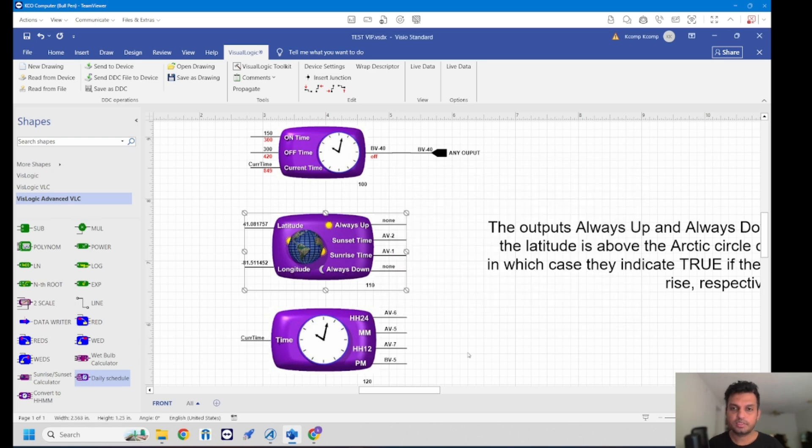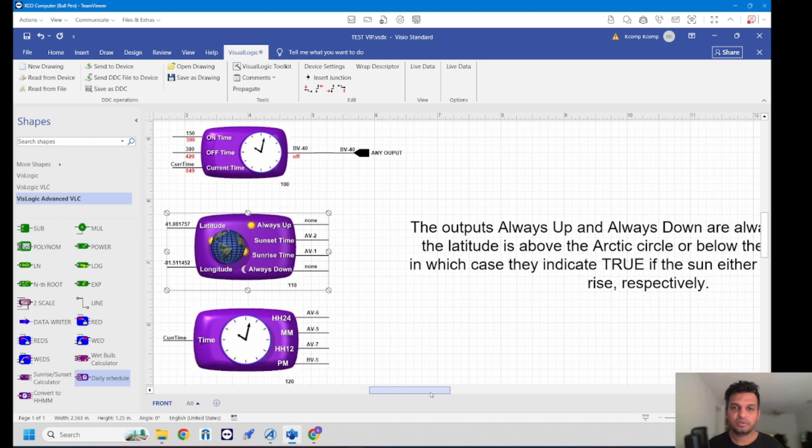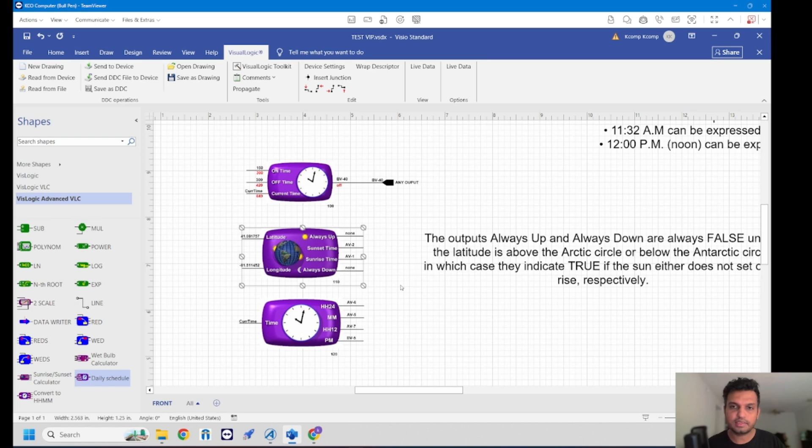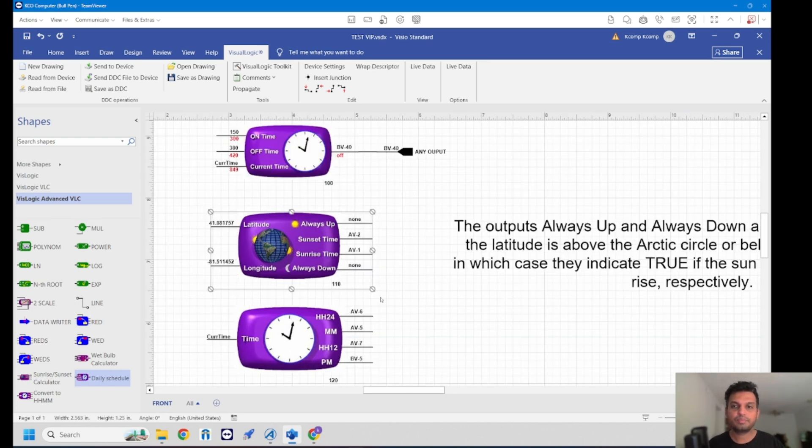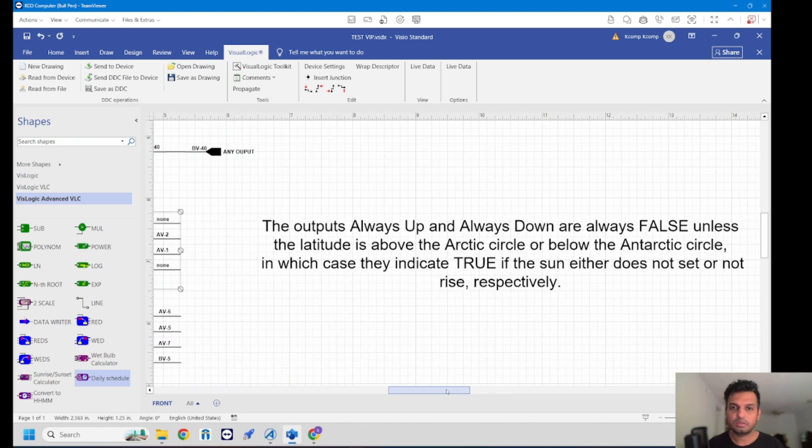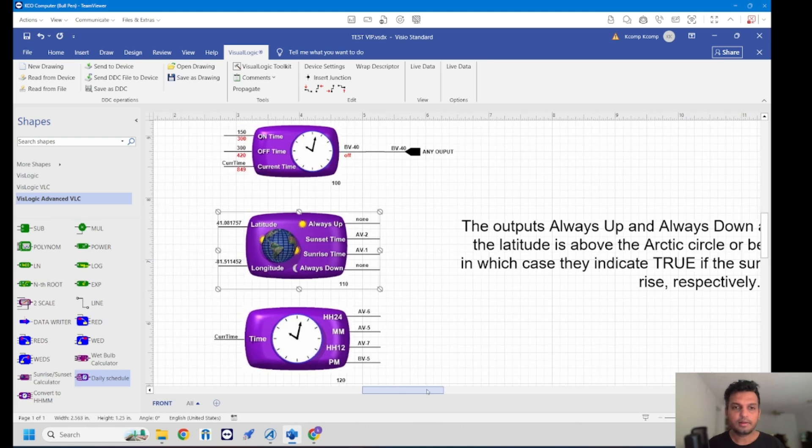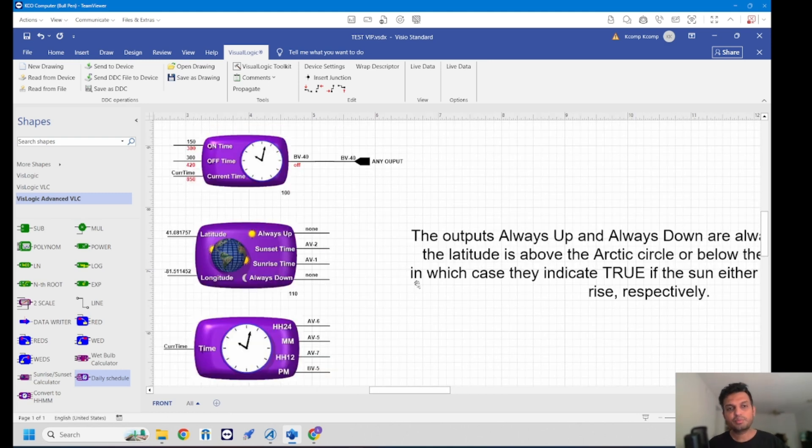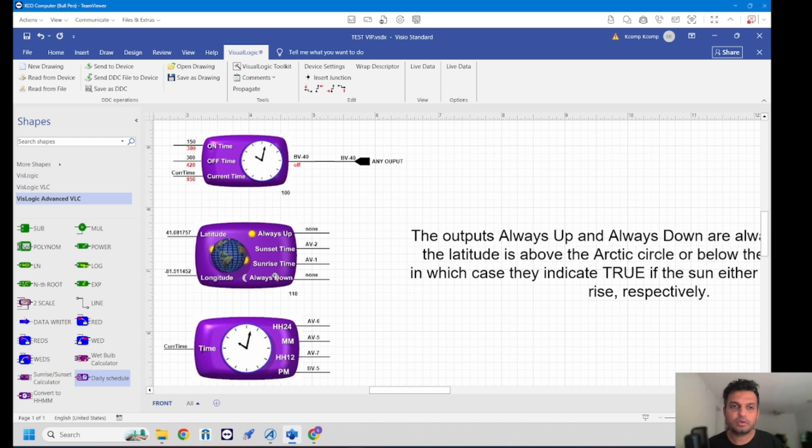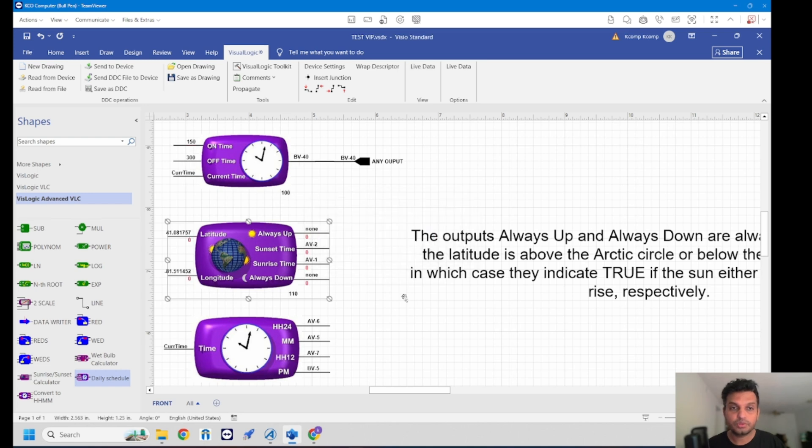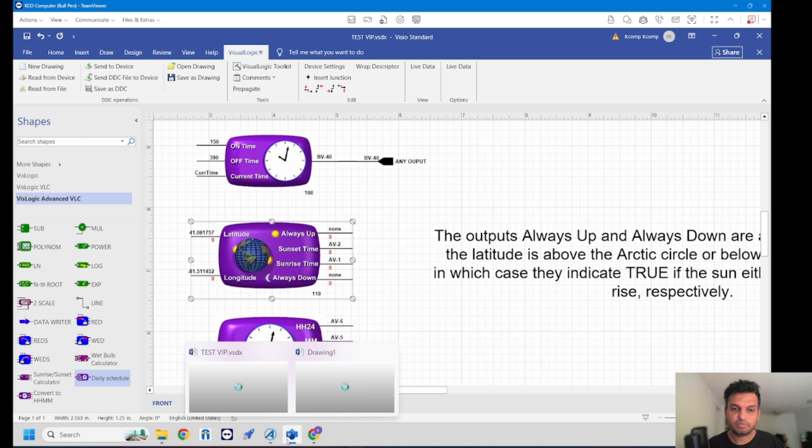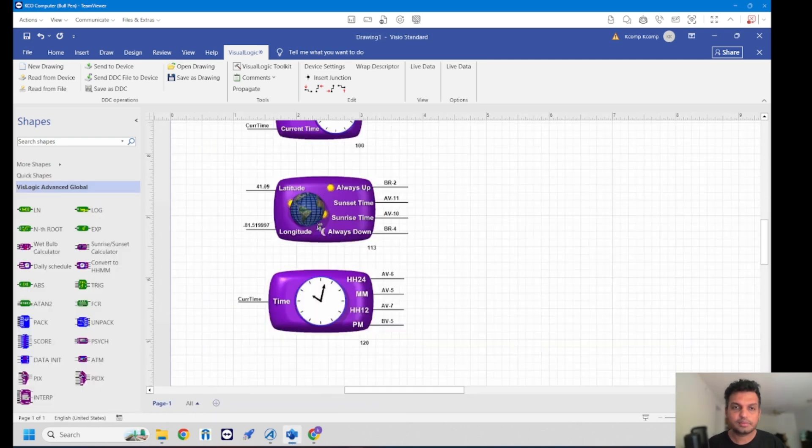Now there is always up time and always down time. What does this do? This is only for the latitude above the Arctic circle or below the Antarctic circle which is always true whenever the sun may not set or not rise depending on either condition. Coming to sunset time and sunrise time and depending on your time zone or the longitude and the latitude, make sure to set your controller at right latitude and longitude and have a correct UTC offset on them, otherwise the function may not work properly.